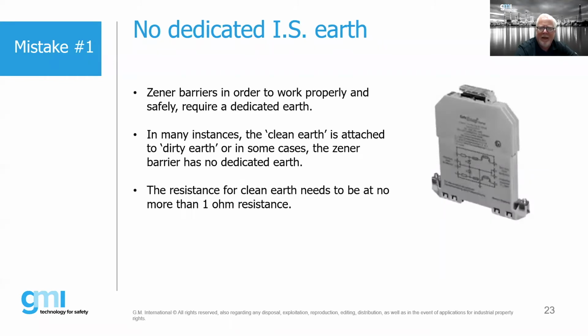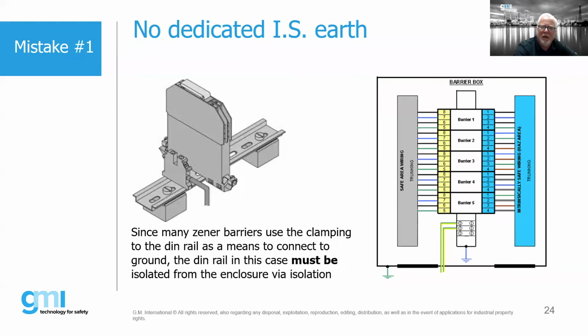And again, that resistance for clean earth needs to be no more than 1 ohm. So when we look at an installation, this picture is showing the attachment of a Zener barrier onto a piece of DIN rail. Well, the DIN rail can also be used as a means for earth. And I've seen some installations where the DIN rail is attached to the enclosure, and if it's a metallic enclosure, then that is typically tied into our dirty earth.